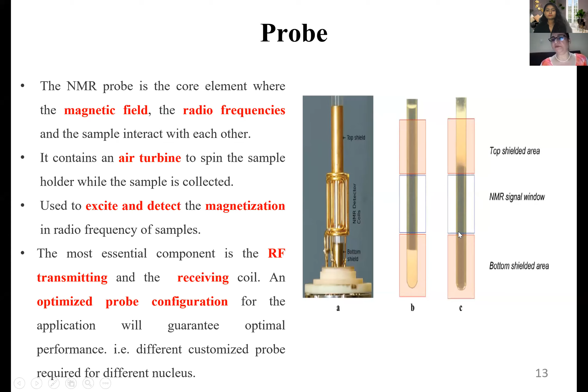So this is the probe, this is the sample tube, and this is the space, also called the NMR signal window, from where the RF signal is passed into the probe. There are RF generators and detectors. The RF radiation is generated by a crystal oscillator. The output of the generator is mixed, amplified, and filtered to produce monochromatic RF radiation, which is delivered to the sample. The pulse might be a rectangular pulse because it is usually given at 90 degrees to the magnetic field of the magnet which is outside. Then the NMR signal originates.